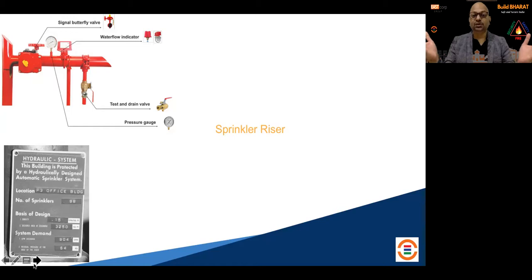picture or image reflected in the drawing but not followed on site. We don't know what this flow switch is going to do - it is connected, but not connected to the fire alarm panel, because it is not shown in the drawing, because it is not inspected at site. Test and drain is there, but you cannot operate it because there is no drain, there is no drain riser connected.